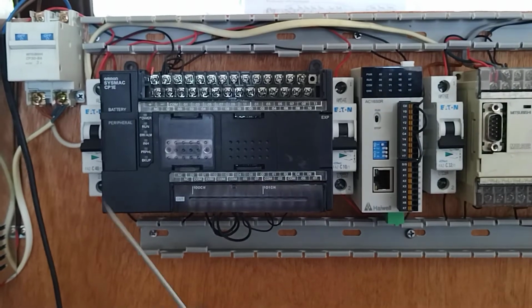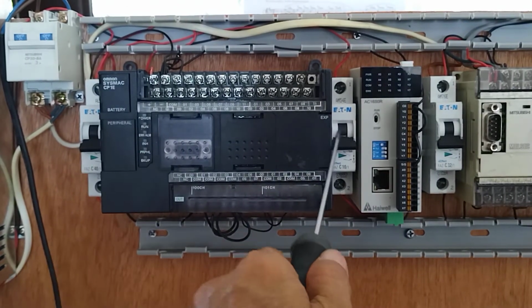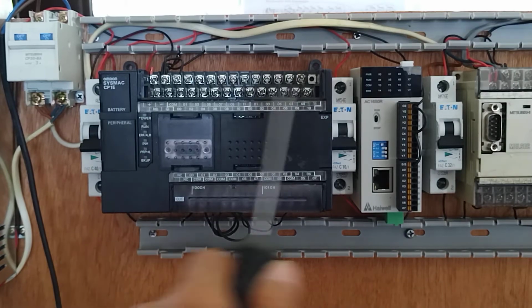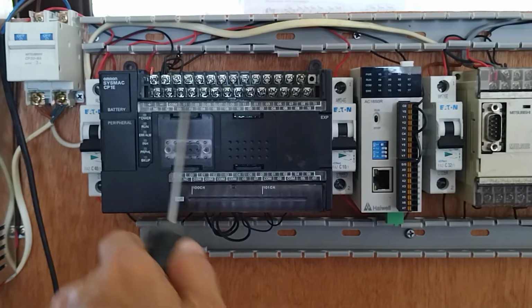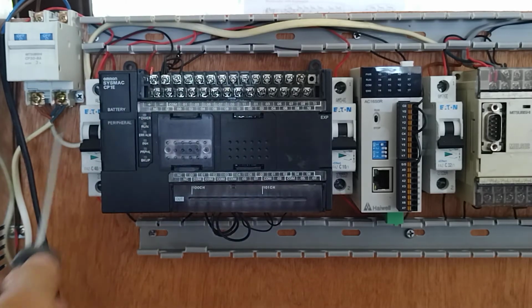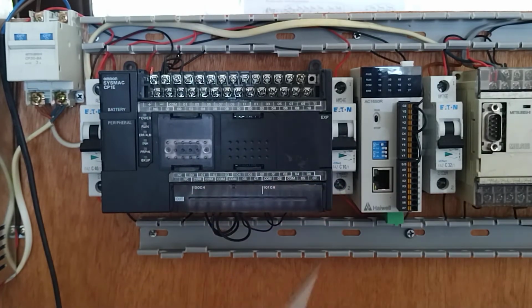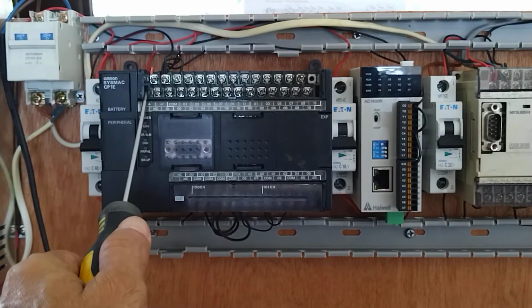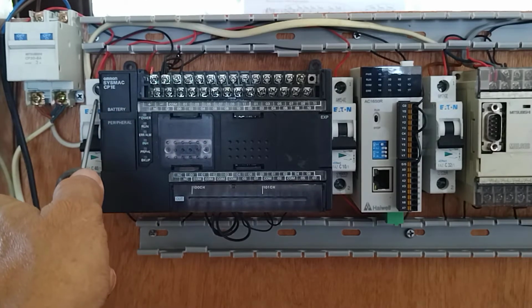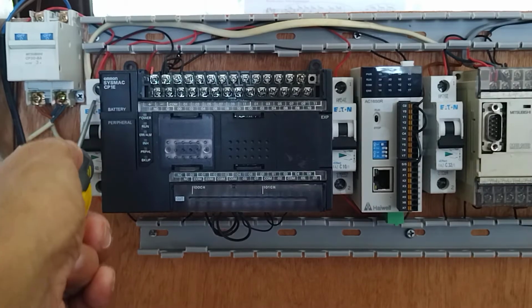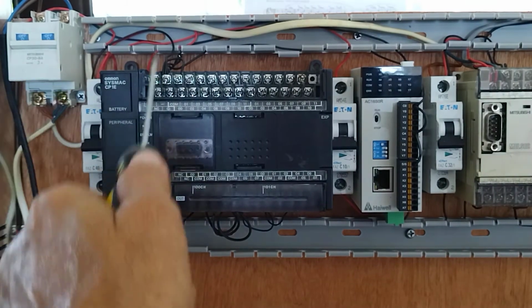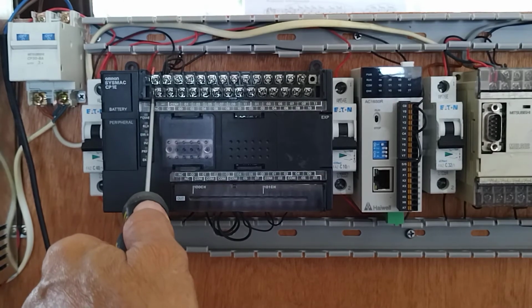Let me move my camera. I also provided here a way to isolate the power supply to each PLC, because if you don't provide a way to isolate the power supply to each PLC system, then when you turn on your main breaker, all your PLCs will be powered up at the same time. So what I'm doing here, let's say I'll be feeding 24 volts, then the positive 24 volts I connect to my single pole circuit breaker, so I can easily isolate the power if I don't need to run that PLC.